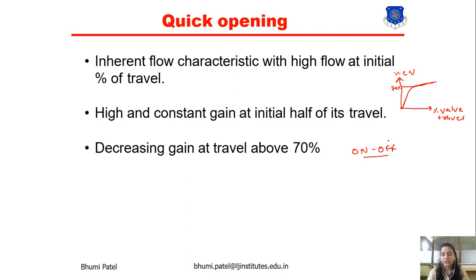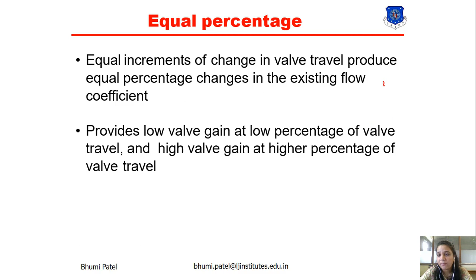Now equal percentage. Now what is the equal percentage? Equal increments of change in the valve travel produce equal percentage changes in the flow coefficient. So for the equal percentage we can get the equal output. It provides low valve gain at low percentage of valve travel and high valve gain at the higher percentage of valve travel. So equal percentage always depends upon how much the percentage of valve travel is increased.